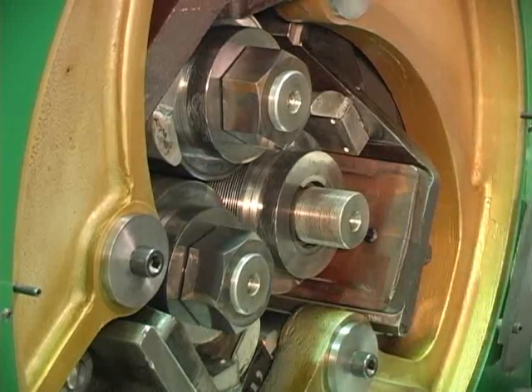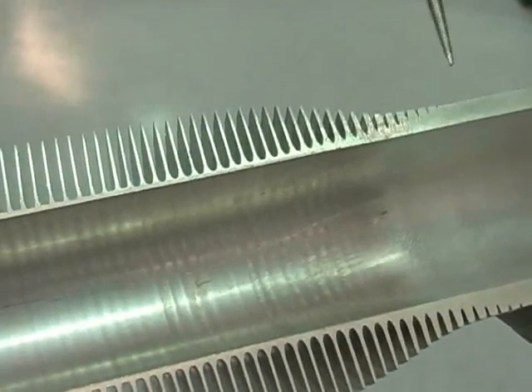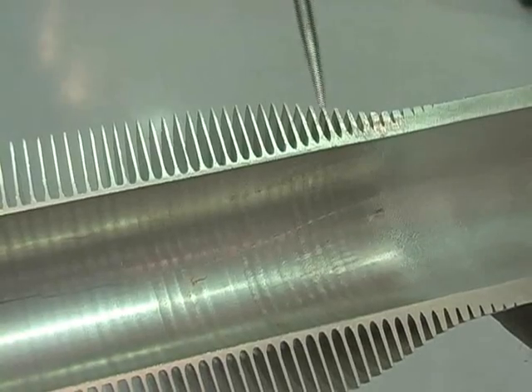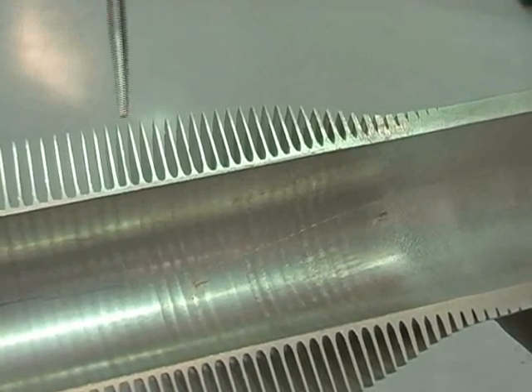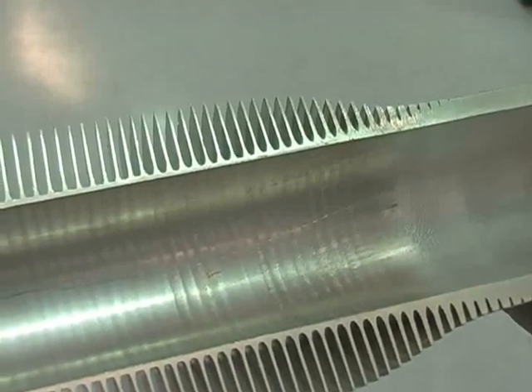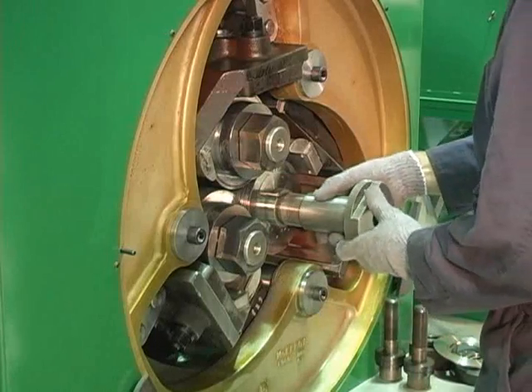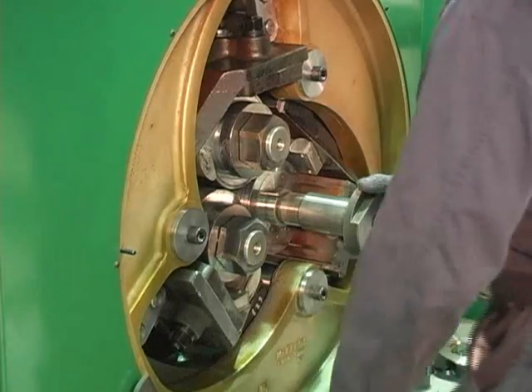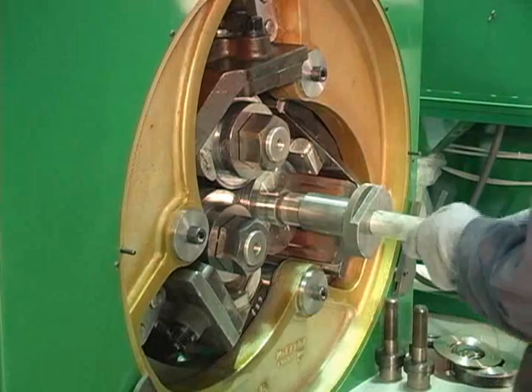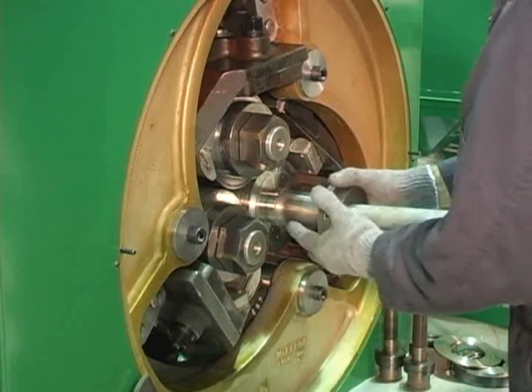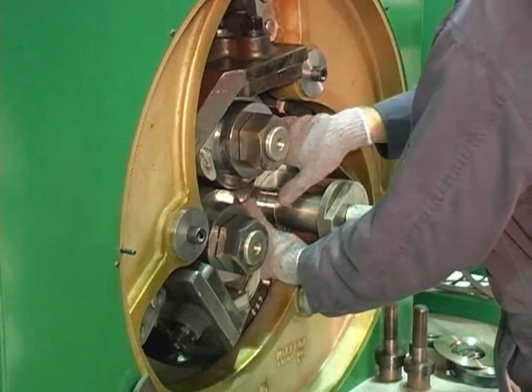As the tube and muff enter the finning head and pass through the discs, the fin is formed out of the aluminum muff, and this developing fin is forced higher by each succeeding disc. Yet for all its size, the head is easily accessible through its cover. In addition, the arbors are not fixed and can be set and reset to the desired depth, thus easily accommodating thin or thick aluminum muff.